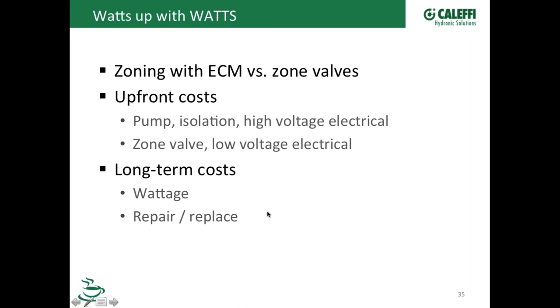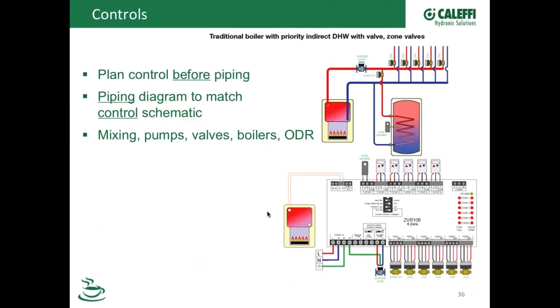You got to think about repairs or replacements, as far as replacing circulator pumps as they fail or replacing actuators as they fail. There's all things to take into account as far as choosing whether you're doing zone valves or circulators, and a lot of good points there.